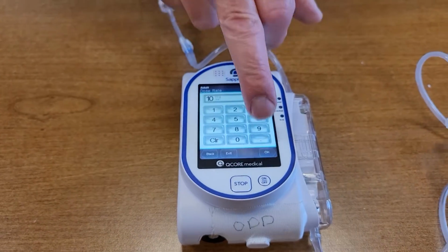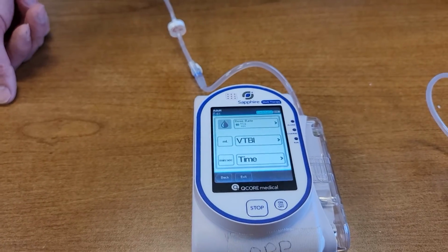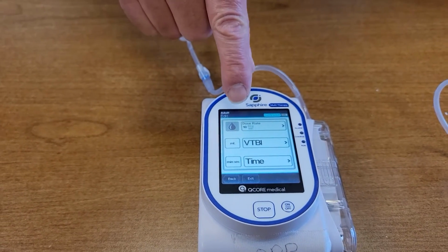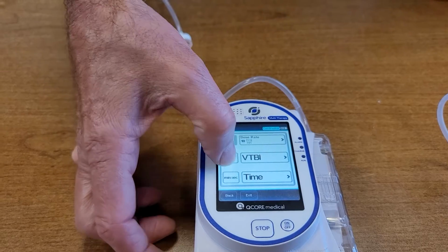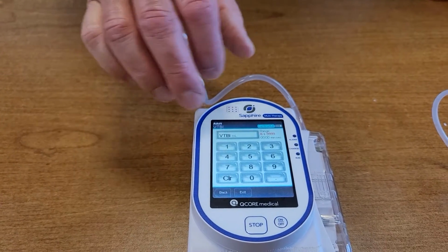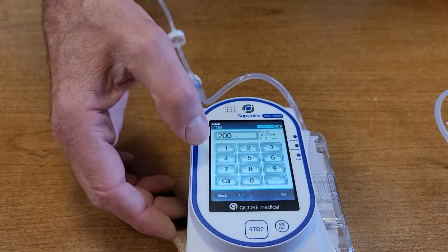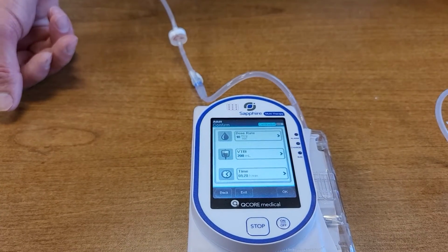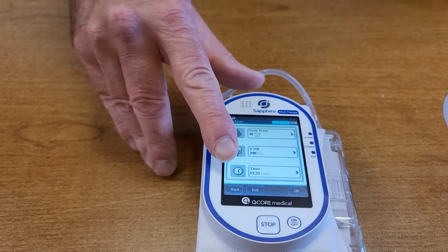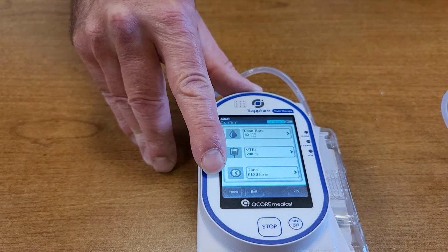It says I'm at 10, I'm gonna hit okay. So I want to run this at 10 mics per minute of epinephrine. Volume to be infused: let's say I have 200 in the 250 in the bag, so I'll go ahead and put 200. And the time.